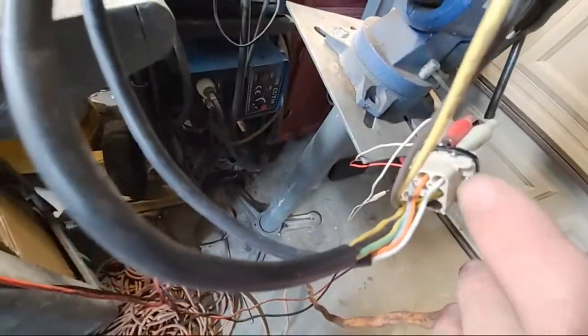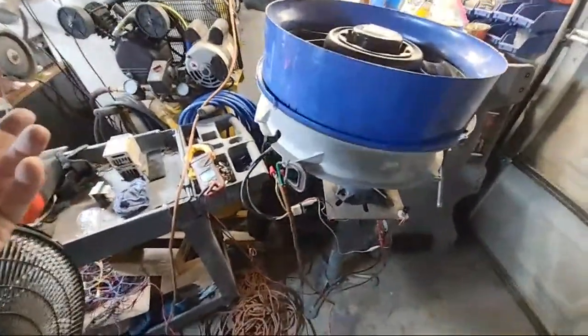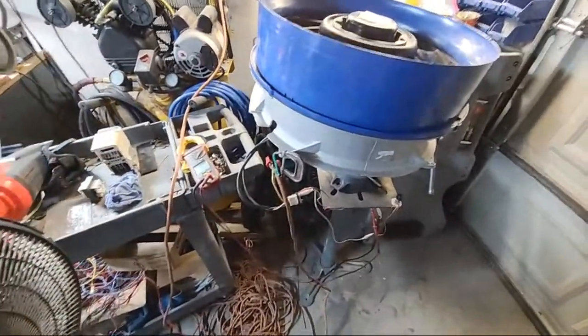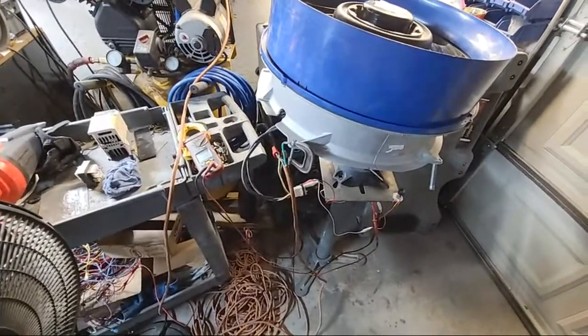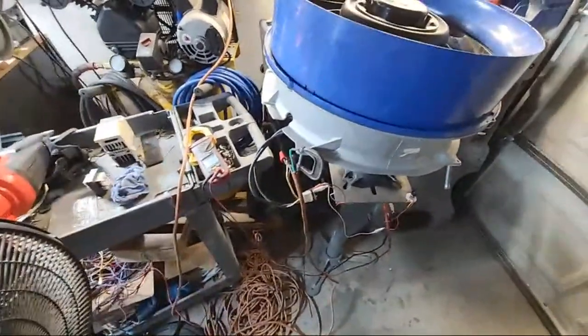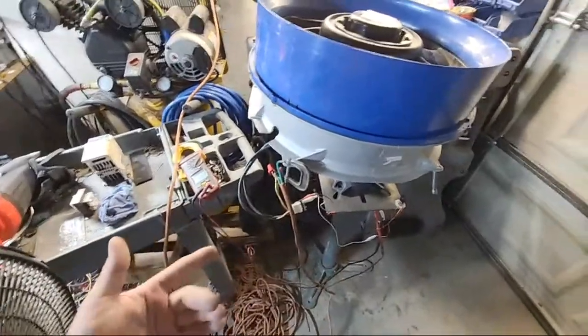Part of this is a 10-volt power supply, and it sends 10 volts back out. So you've got common, which is white, 10 volts, which is orange, and gray is your signal. It's like a 2 to 10 strategy - basically might be more like 1 to 10 because I saw it spin when I put less than 2, but that's basically what it is. So that gives it a reference.